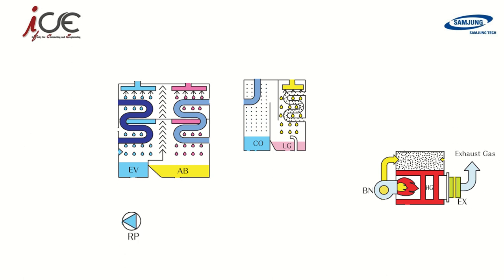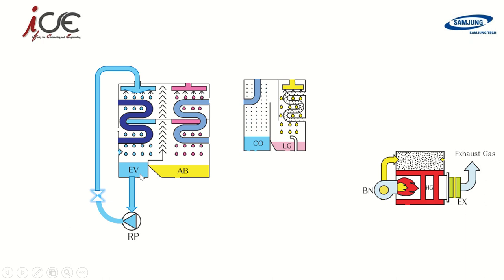The following steps explain the cooling procedure and all stages of the cooling process. The cooling process takes place in the evaporator. The refrigerant pump sucks the refrigerant — which is distilled water — from the bottom of the evaporator and spreads it again over the chilled water pipes, indicated here in dark blue. This occurs at a pressure inside the evaporator of about 6 mmHg, which equals 0.8 kilopascal absolute pressure, much lower than atmospheric pressure.